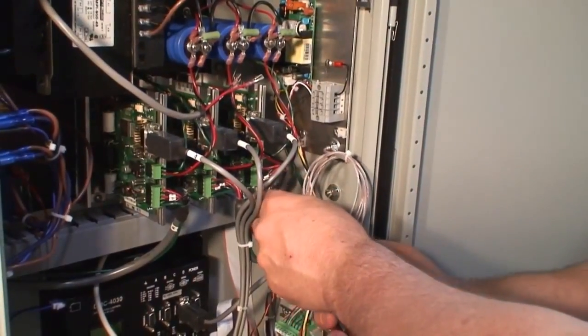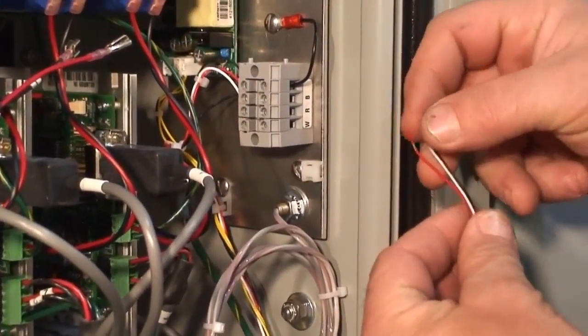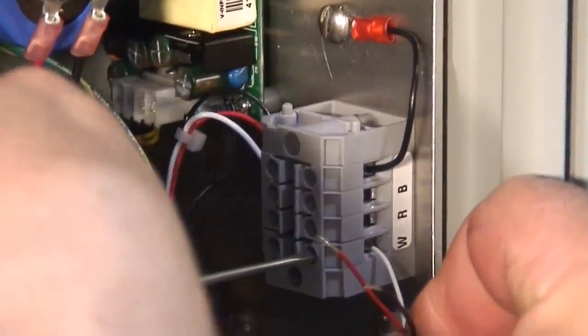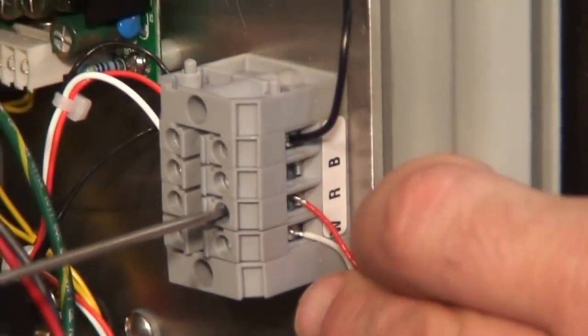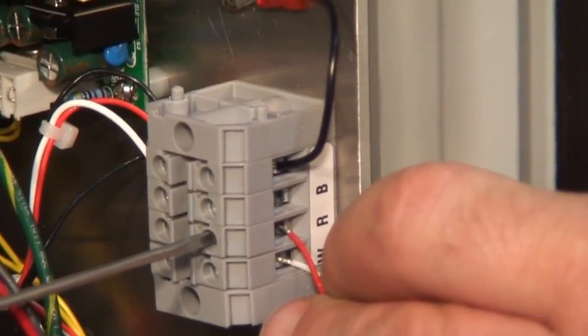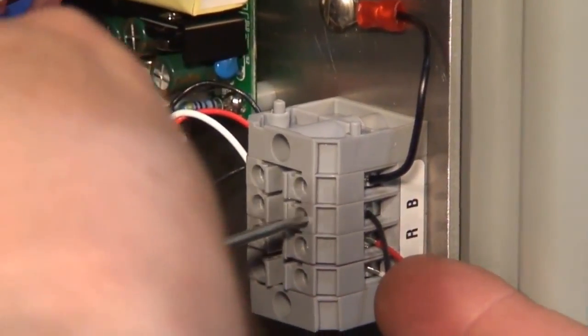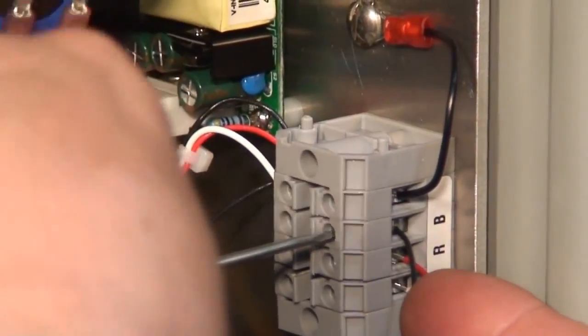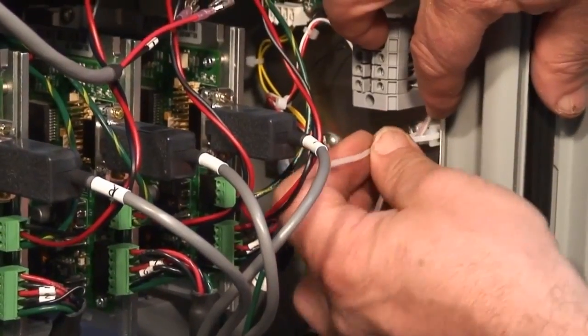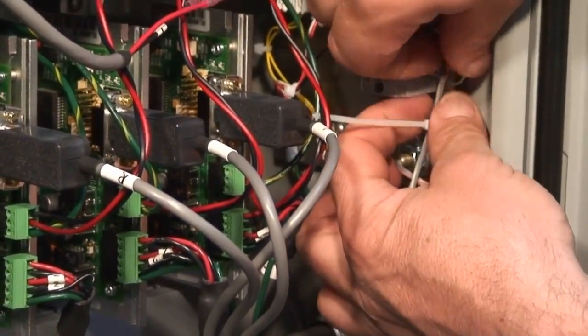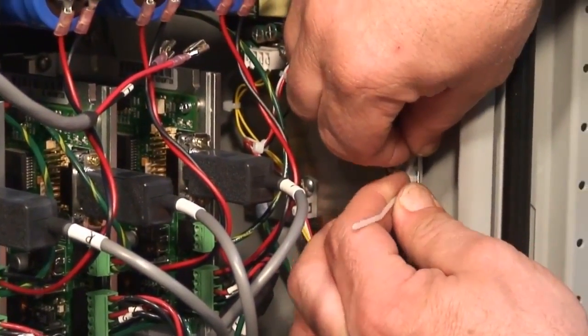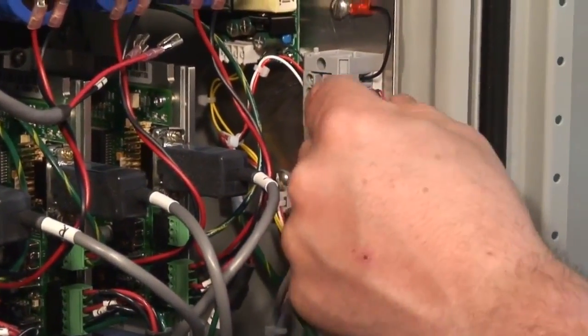Now remove the insulation from the three wires. Put them in the terminal block as shown. The white wire goes in the W terminal, the red in the R terminal, and the black in the B terminal. Tighten all three screws when you're done using the supplied small screwdriver. Secure the entire bundle to the anchor point provided on the power supply base plate. This provides strain relief for the three wires. You don't want the weight of the bundle hanging on the wires.